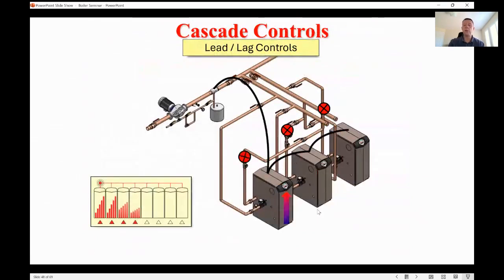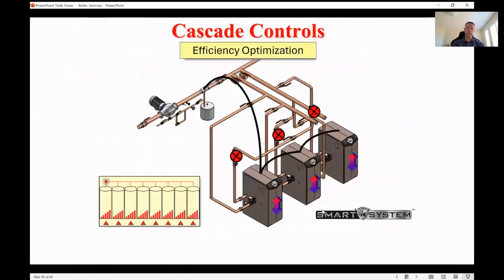Now, as I said, I like talking controls as well with these boilers. They've got very advanced controls in there, and a lot of people just put in the boiler, put it on, maybe set the set point or the indoor or outdoor reset and leave it at that. There's so much more to most of these boiler controls these days. Most of them have built-in sequencers for multiple units. The most prominent control strategy out there is lead lag. First one goes on, when you need the second one, once that's past its 100% firing range, it'll turn that second boiler on and so on. They'll usually rotate that lead boiler every 24 hours, or a lot of them are actually programmable how you do that. So that's one option out there.